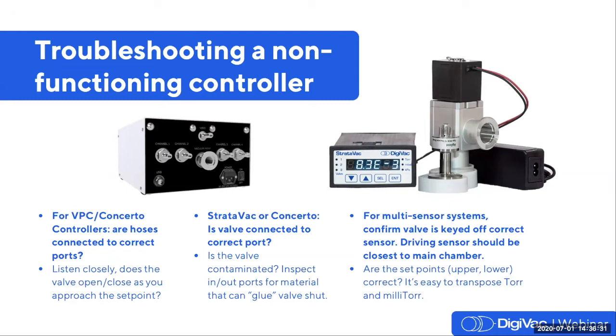Ensure your pump and vacuum system are connected to the correct ports on the back of the gauge. If a pump is attached to the system port or vice versa, the gauge will not control vacuum. Listen closely to the sound of the valve solenoid over the noise of the pump. Can you hear it activate as the vacuum level approaches the set point? Make sure the gauge is connected to the right port on the back of the gauge. In the case of the DigiVac, the valve card has 2 connectors and the valve is plugged into the top. If you're using the valve to control a system that is potentially contaminated, remove the valve from the system and inspect the in and out ports for oil that may be gluing the valve closed.